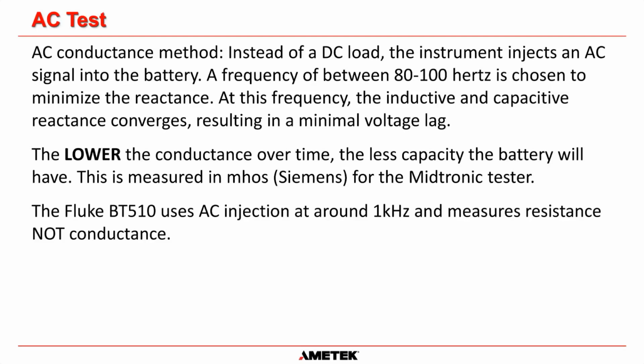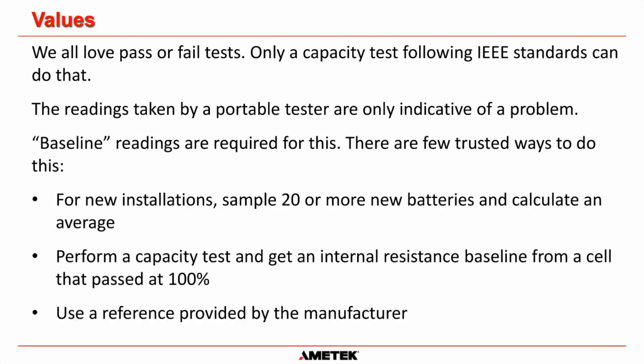And just to confuse things, the AC load testers don't have a standard. So for example, that bottom line there says the Fluke BT510 uses AC injection at around 1 kilohertz, and it measures resistance, not conductance. So the Fluke BT510 is injecting a signal into the battery, an AC signal, but the calculation they do is the internal resistance. So as the internal resistance goes up, the capacity of the battery will go down. So yes, it is confusing, but if you have any doubts, read the manual of the test device that you have, and it should explain in more detail what it is doing. Okay.